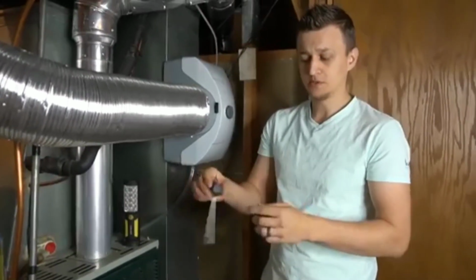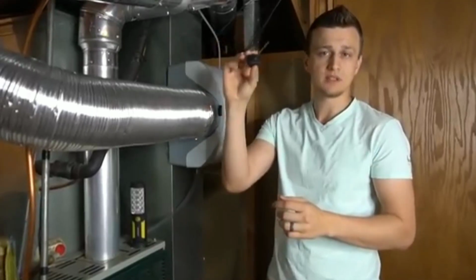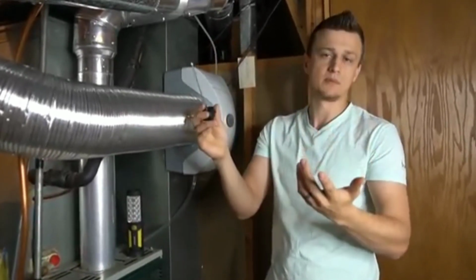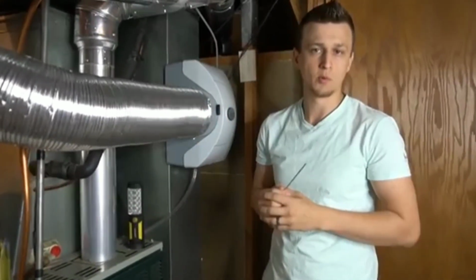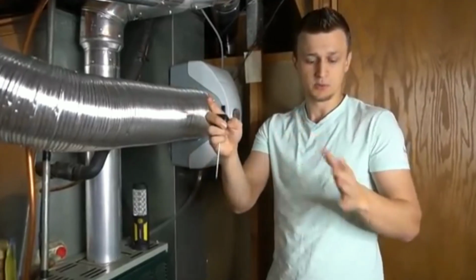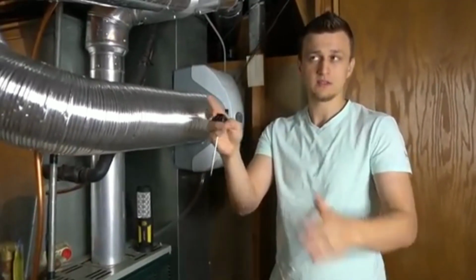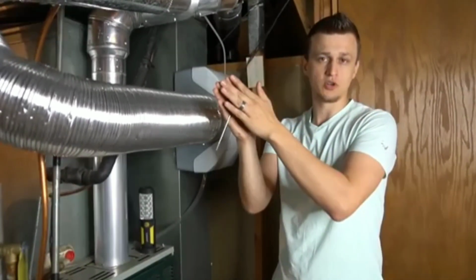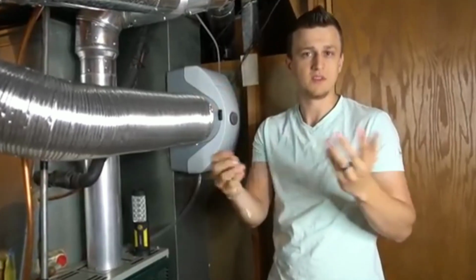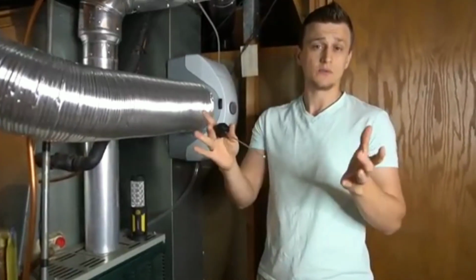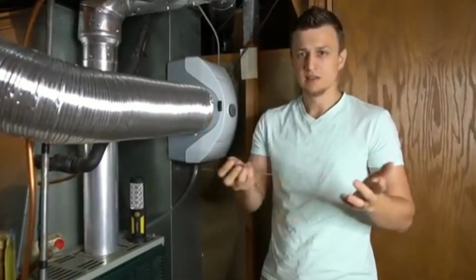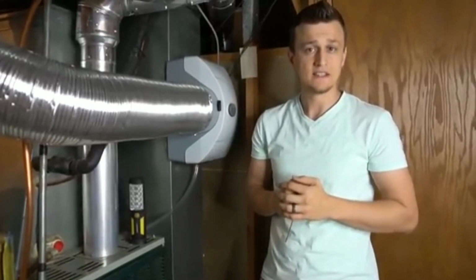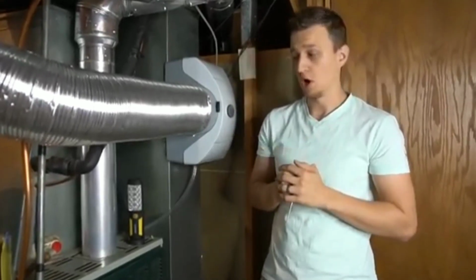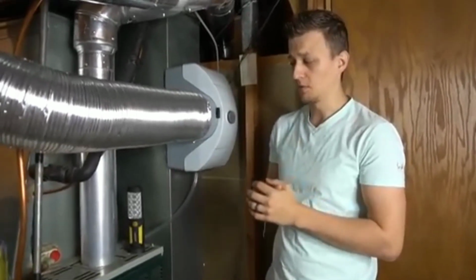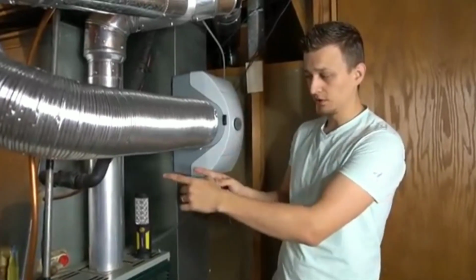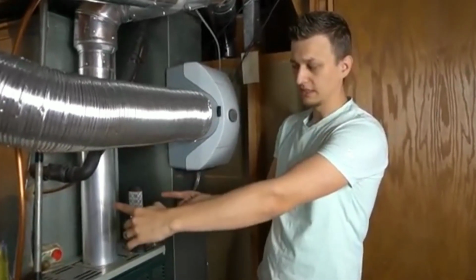Record that temperature and then take a temperature of the ambient air, or basically the room temperature, you know, in your living room or whatnot. And the difference between the air coming out of the vent and the air temperature in your room should be that 15 to 20 degrees. Now, if you have less than 15, let's say yours is like 6 to 10, that means you are having a problem. The most common problems are either the A coil, that radiator looking thing.